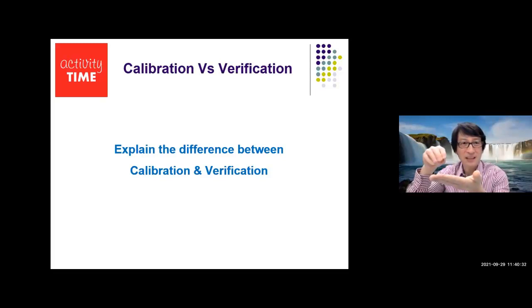Right? How do you do it? They will read your torque meter value. For example, the reading gives 10.1. But the standard that they're using for calibration, the known value, is, for example, 10.0. So that means the true value of the torque is supposed to be 10.0. But when they use your torque meter to measure, it gives a value of 10.1, for example. So 10.1 is the value given by your torque meter, and 10.0 is the true value of the actual torque that is applied onto the torque meter. So 10.1 versus 10.0, there's a difference of 0.1. You see that?